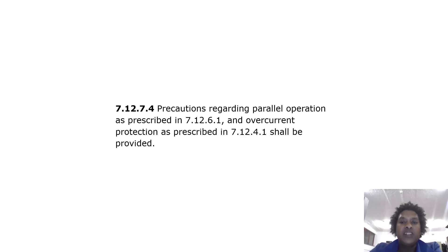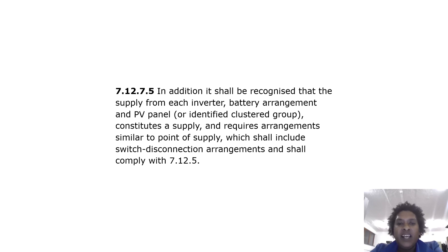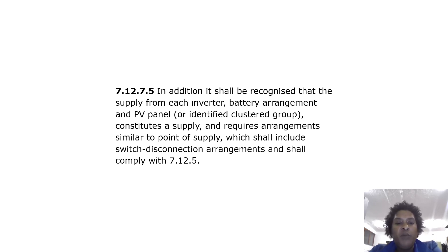Precautions regarding parallel operation as prescribed in 7.12.6.1 and overcurrent protection as prescribed in 7.12.4.1 shall be provided. It shall be recognised that the supply from each inverter battery arrangement and PV panel or identified clustered group constitutes a supply and requires arrangements similar to a point of supply, which shall include switch-disconnection arrangements and shall comply with 7.12.5.